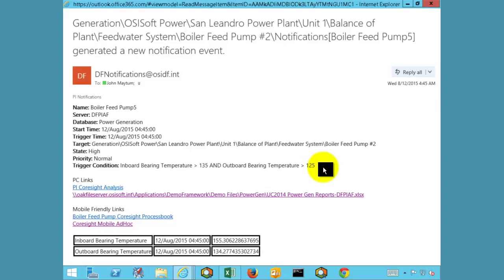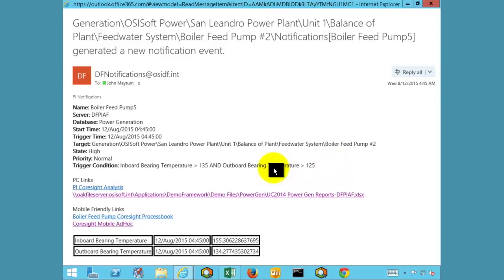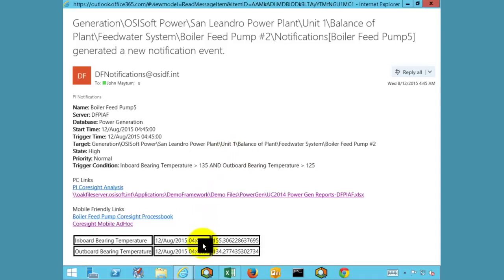In this example, the PI System has sent us a notification via email. This notification provides key information that allows us to determine what operating conditions were out of band. The trigger condition, asset information, as well as other pertinent data are all embedded in the email. The notification has also provided links to existing displays and reports that are useful in troubleshooting issues with this boiler feed pump.